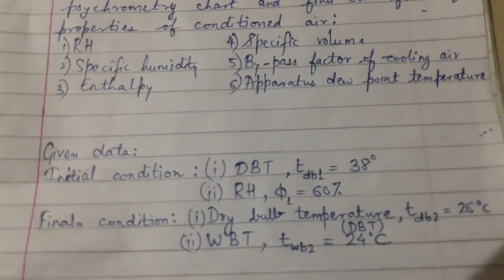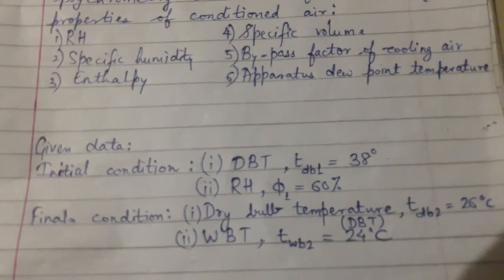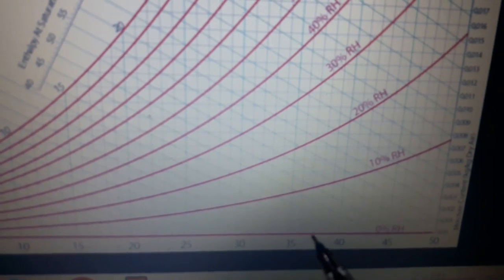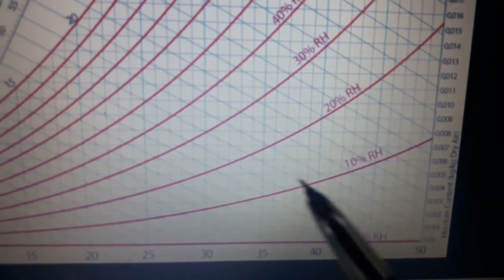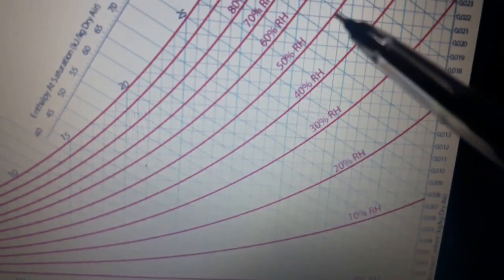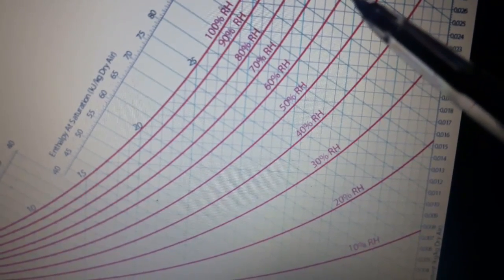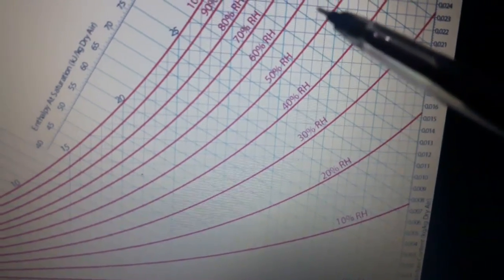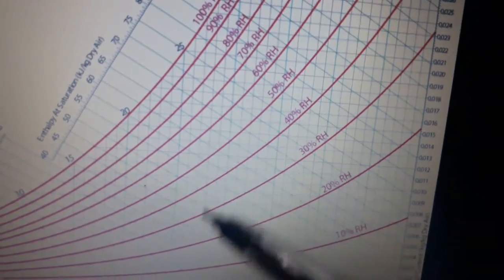We have to first mark the initial and final conditions on the psychrometry chart. I have taken a simple psychrometry chart to explain. First, locate 38°C on the dry bulb temperature axis — this is 35, 36, 37, 38 — and draw the line upward. Then find the RH = 60% curve and mark the intersection point where the 38° line meets the 60% RH curve.